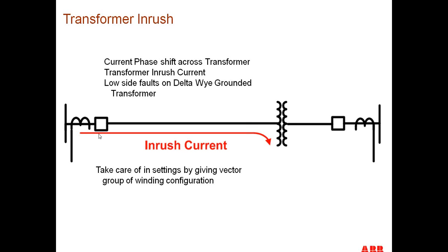So the things we need to worry about is inrush current that's flowing on one side of the transformer, and so it goes through one CT and not the other CT. We also need to worry about, if this happens to be a delta-wye transformer or a wye-delta transformer, then the current at one CT is not in phase with the current on the other CT under normal conditions, and we need to account for that phase shift across the transformer. And if we have low side faults on the secondary of the transformer, the CT on the low side may see this fault, but because it's a delta-wye transformer, the CT on the other side doesn't see the fault because of the current being trapped in the delta. So these are the things that we worry about in transformer protection, and we also would have to worry about that in using a transformer terminated line, having a transformer in our line section.